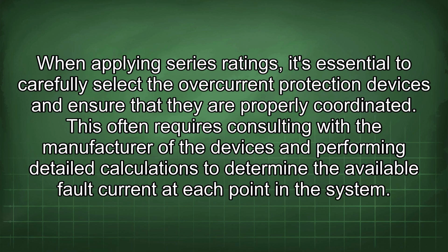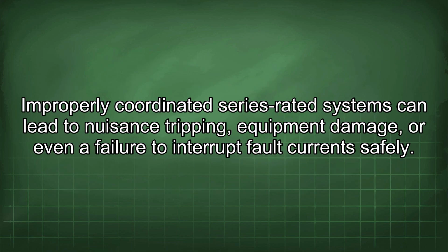When applying series ratings, it's essential to carefully select the overcurrent protection devices and ensure that they are properly coordinated. This often requires consulting with the manufacturer of the devices and performing detailed calculations to determine the available fault current at each point in the system. Improperly coordinated series-rated systems can lead to nuisance tripping, equipment damage, or even a failure to interrupt fault current safely.